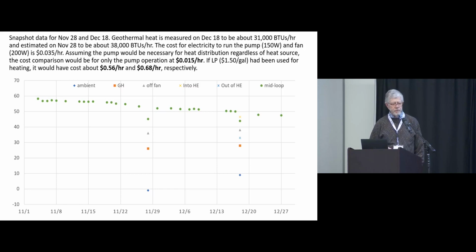There's a device I recently became familiar with. A company in San Jose, California has produced it and is just hitting the market now. It's a combination pump and heat exchanger that drops down a well. If you bore two wells, you pump out of one through the heat exchanger and deposit it in the other well. The heat exchanger has another loop that goes to the point of use.